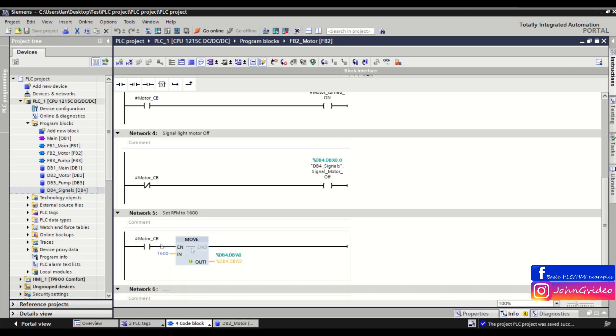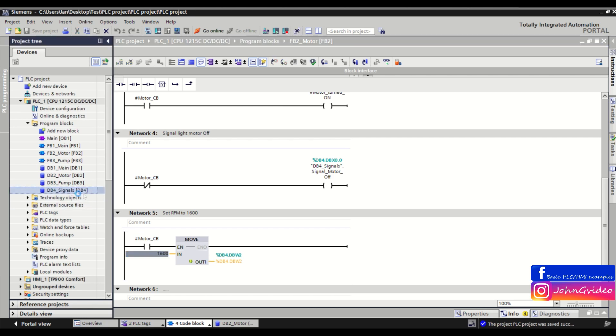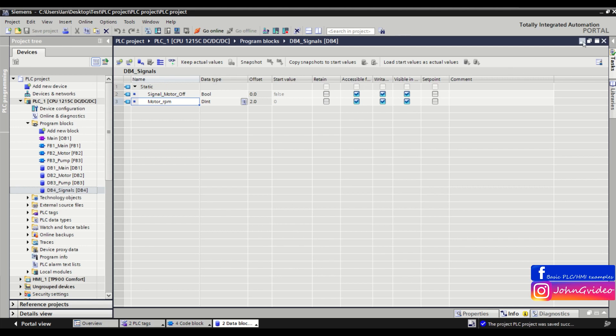For example, you use only the first word of this double integer, where you write the motor rpm — in this example it is 1600. When the circuit breaker for the motor is turning on, you write the rpm value to the first word of the variable motor rpm. And there is the problem — when you use it like that, you have a problem with cross references.